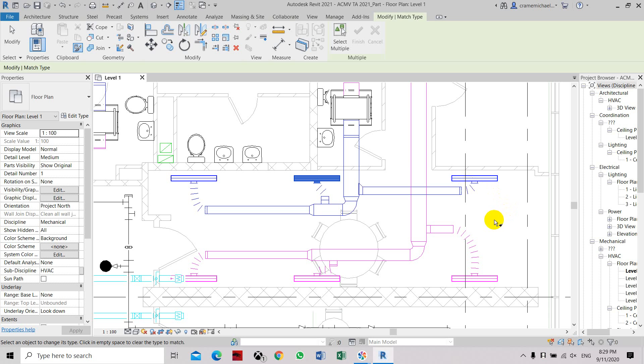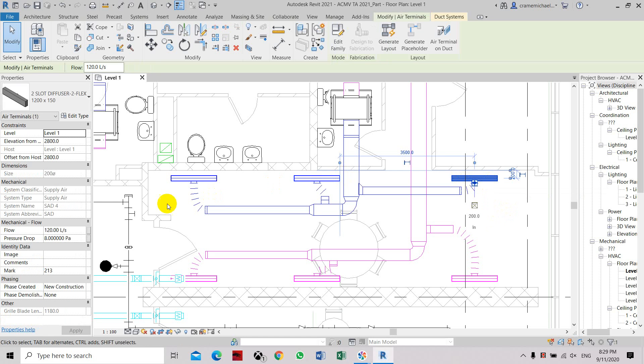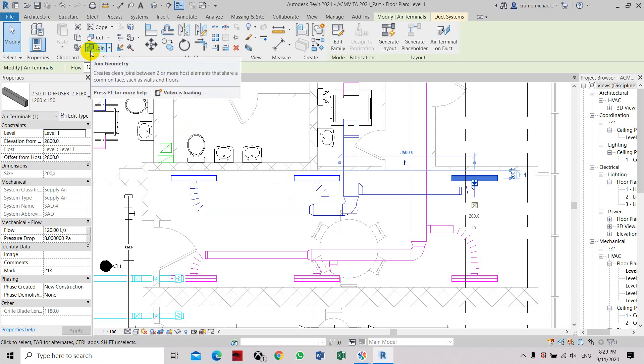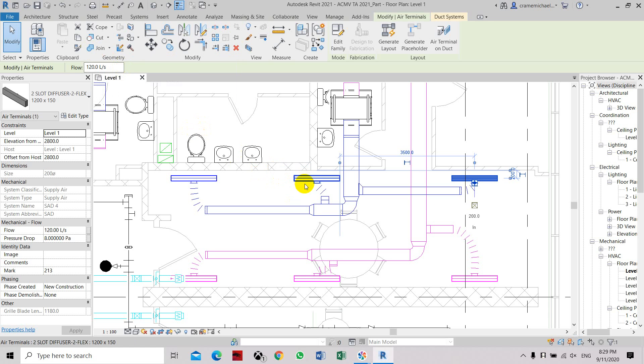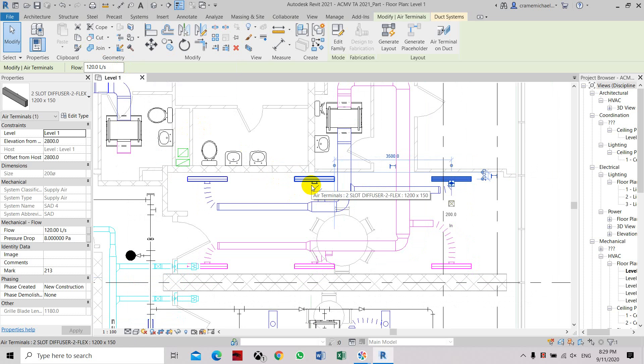Click escape twice. Now if you select the third grill, you can see under the airflow or mechanical flow, it's set at 120 liters per second. So there's two ways of doing it. Either you do it manually or you can use the match type properties tool if you have multiple grills that you need to set the airflow with the same capacity.